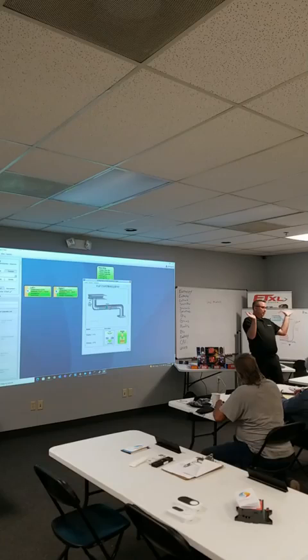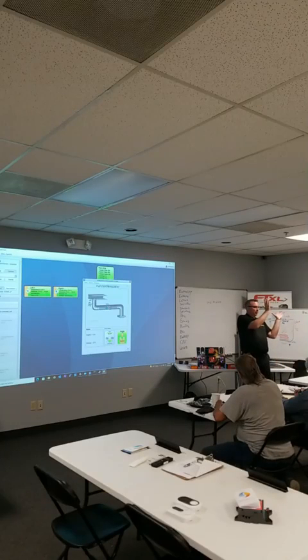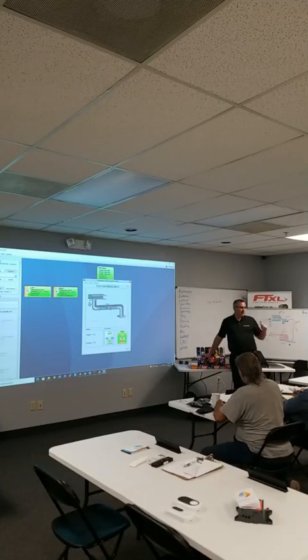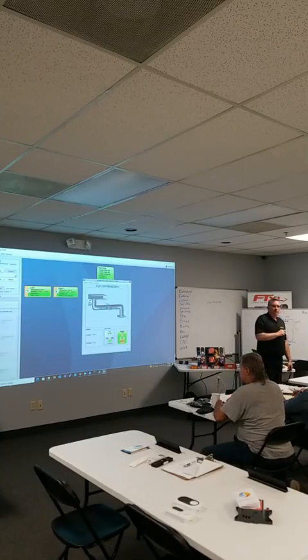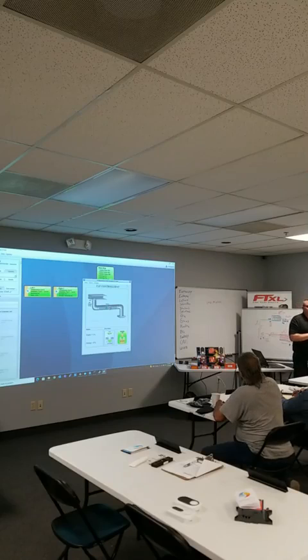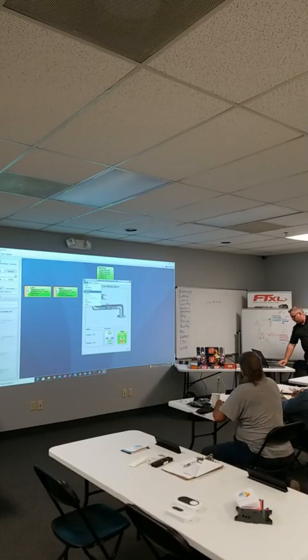So 0% open, 100% open. If you move it manually, even if it's 0 to 45, it no longer knows where it is, because it sends a command and follows its own feedback. If you have poor duct design or too much flow noise, you could change that with the stops: power it down and make it 0 to 22%, so it only goes a quarter open for full open. We did that for noise.